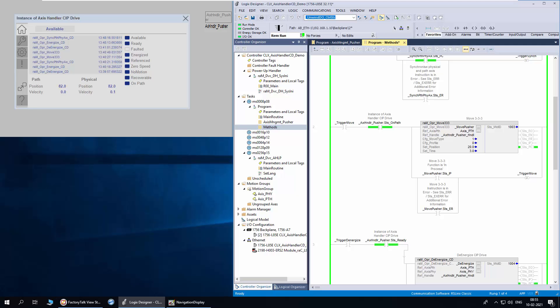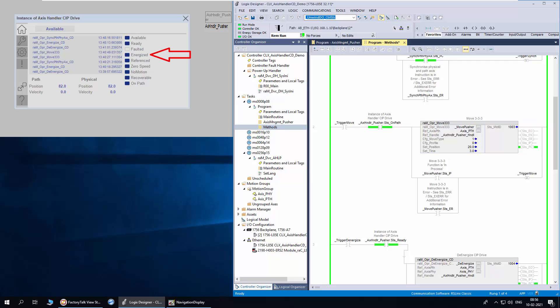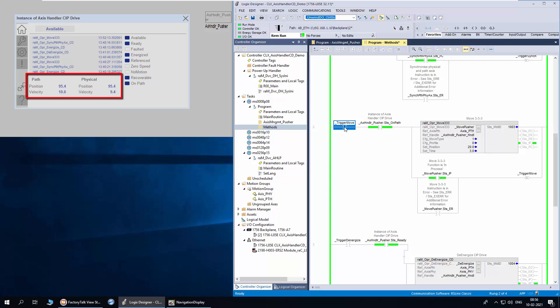I will demonstrate how physical and virtual mode work. First, I will trigger the move333 method to show how path and physical axis work in physical mode. The physical axis is already energized and in sync with the path axis, thus the on path status is on. I will trigger the move333 method. You can notice that both path and physical axis are moving together as the physical axis is geared with the path axis.